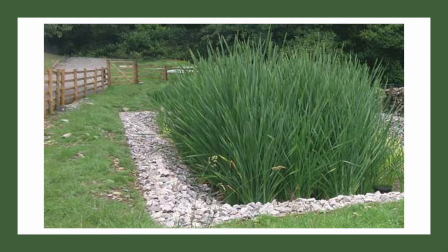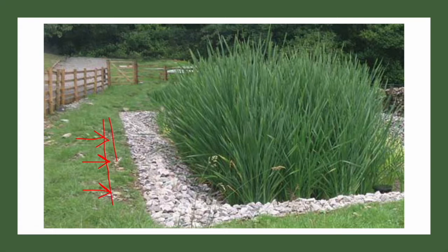The components of a constructed wetland are very simple. What you need is basically gravel — what you are seeing here is gravel — and reeds, these plants, and some basic mechanical components like a pipe. Since we are covering a horizontal flow constructed wetland, the flow will enter horizontally through a perforated pipe placed under a layer of coarse gravel, which will disperse the wastewater flow into the wetland.